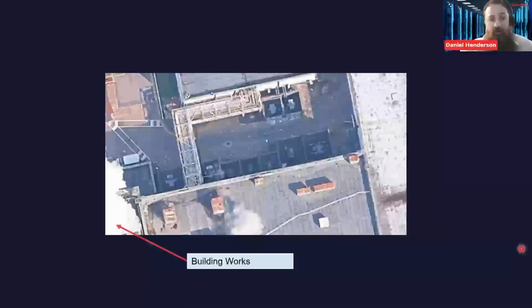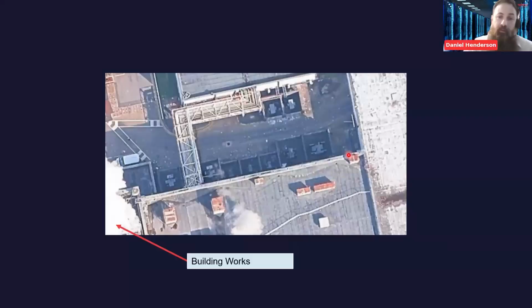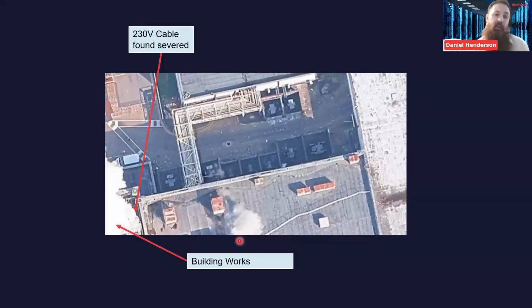So I've followed the cable from there. This is where the building works were taking place, on the west side of the building. Switch rooms here, and the LV supply comes from somewhere around this area. But I've identified around here that the 230-volt AC supply was severed.